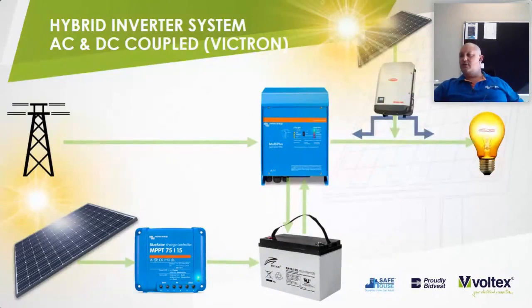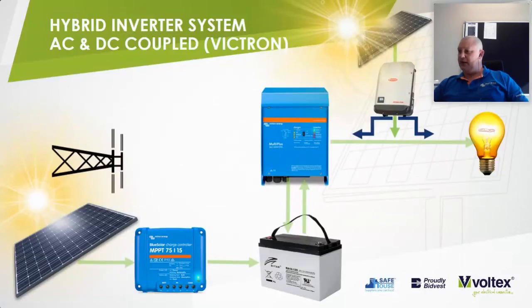runs along with it. So your AC inverter is designed for specific loads, to power the loads directly where the loads are powered. And the charge controller is there for two reasons: to keep the battery charged, and also in the event of a mains failure, where the battery has completely discharged. Your MPPT is your fail safe, where when the sun comes up, the inverter with the charge controller will start charging the batteries, and when reaching a certain voltage, your inverter will switch on the power output, and in turn power up the grid tie inverter, enabling it to feed power directly to your loads and also in reverse back again to your battery for charging. In the event of mains failure, everything stays active.